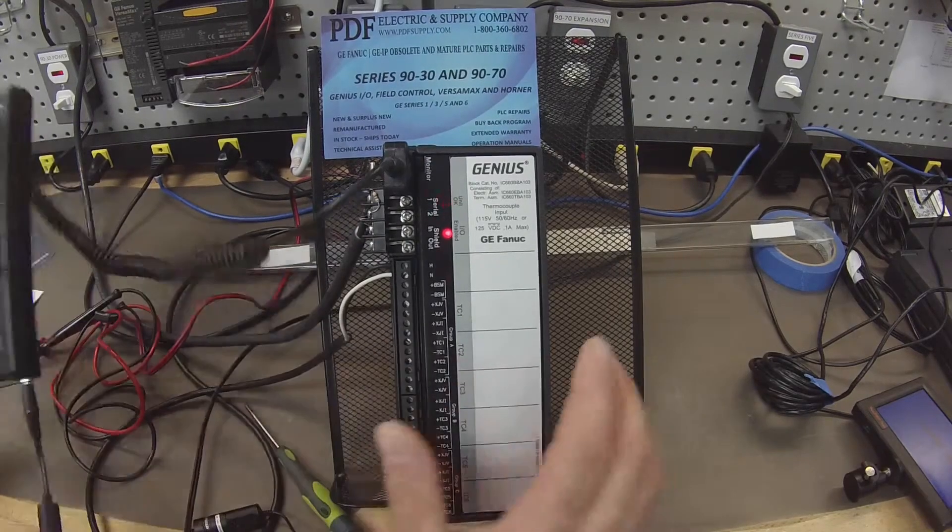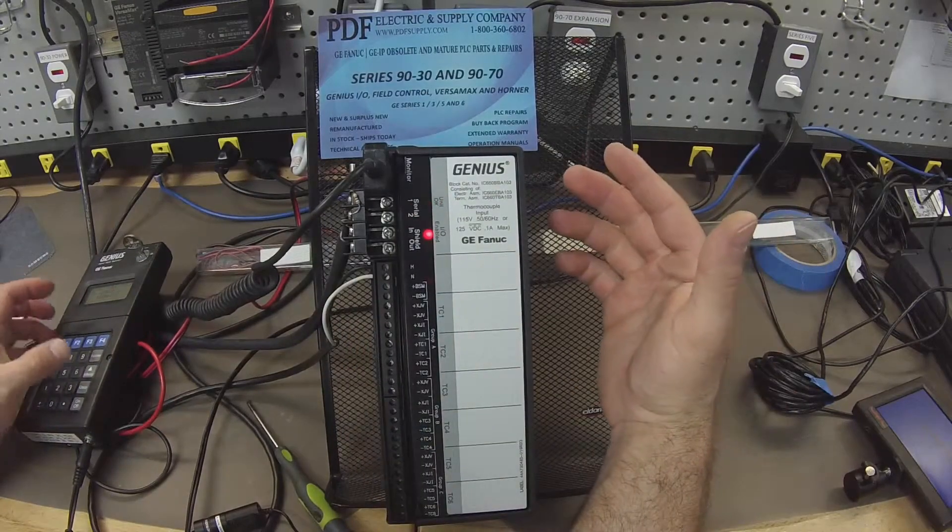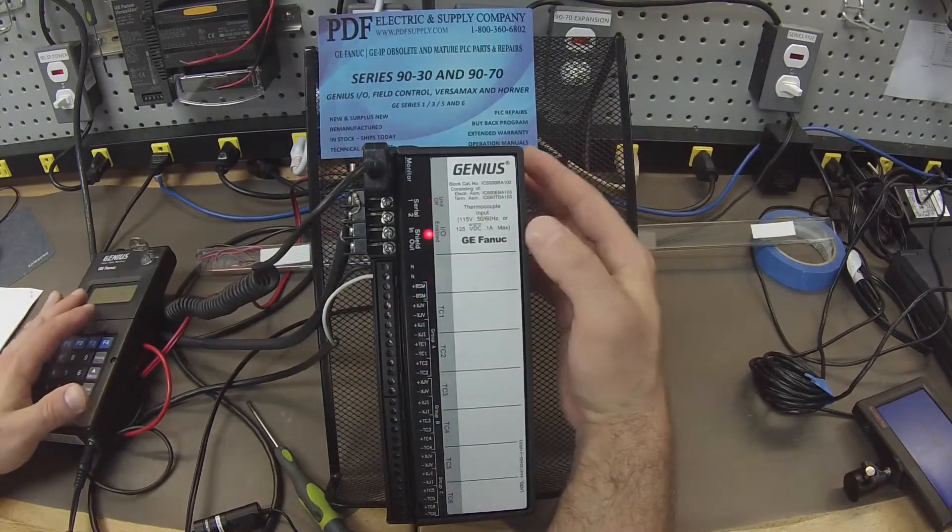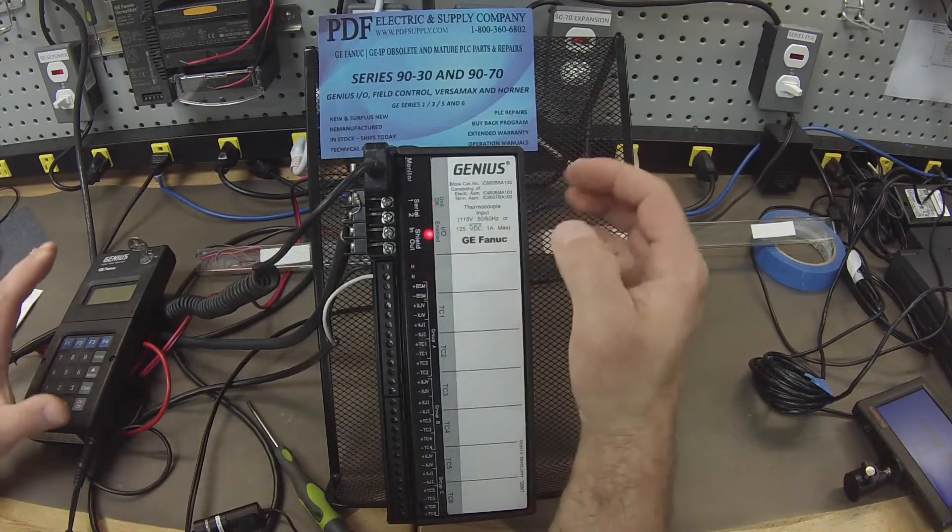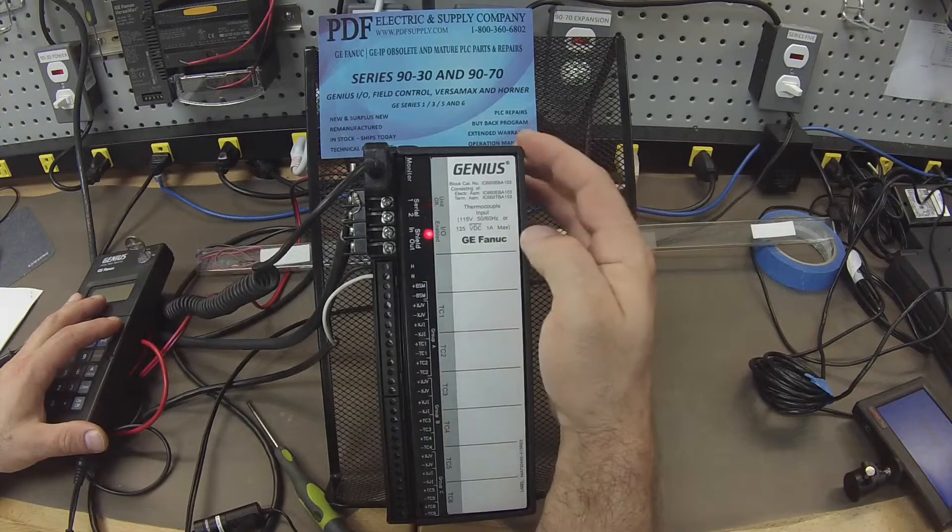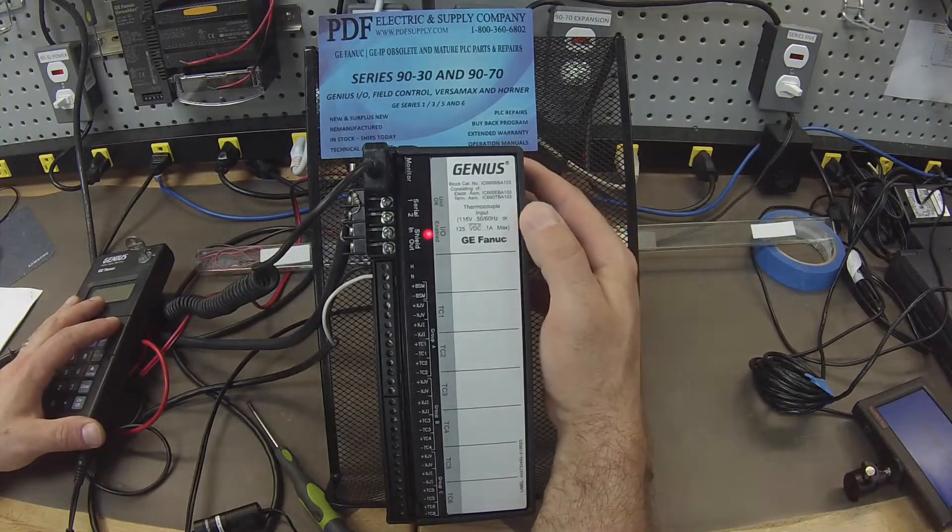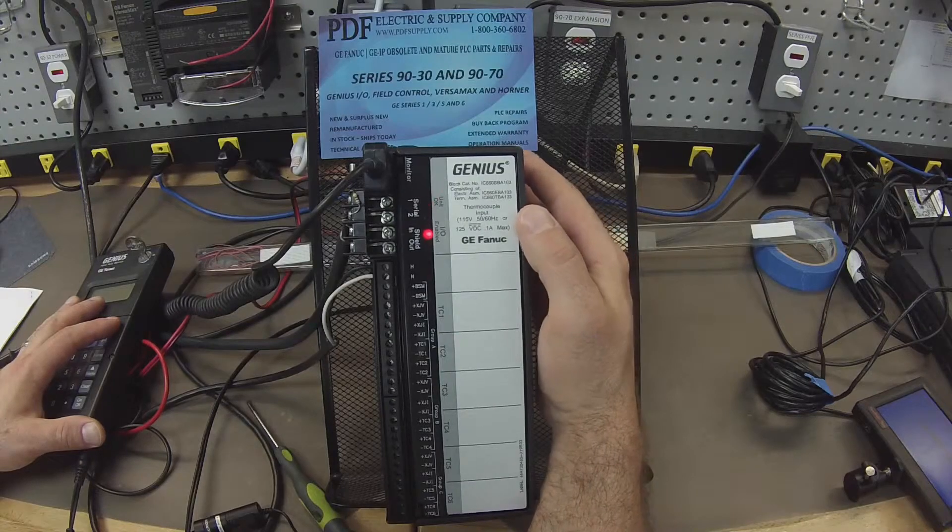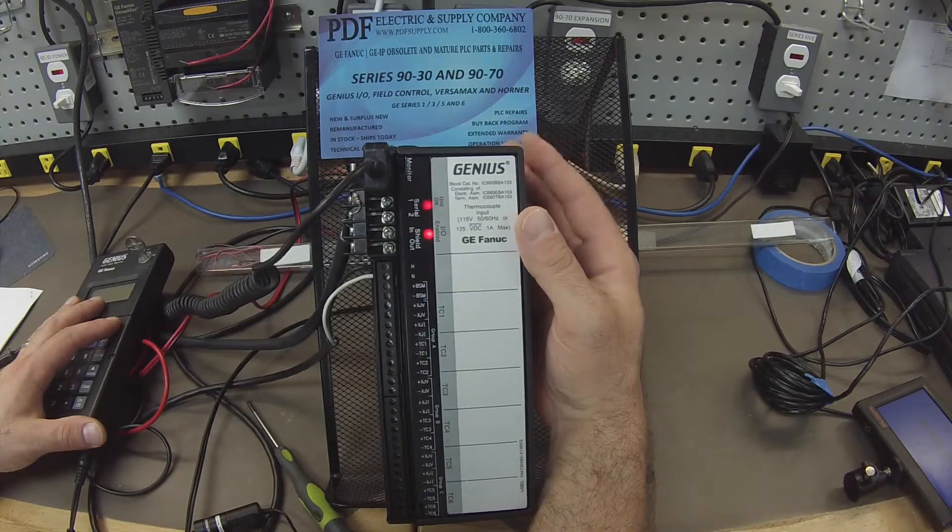Now if you power up your Genius Block and you don't get any lights on, or if you're using the handheld monitor and you go to program the ID and you get a question mark and you're unable to store or program any information in the Genius Block and it's not responding, then that's something we typically repair that we see quite often.